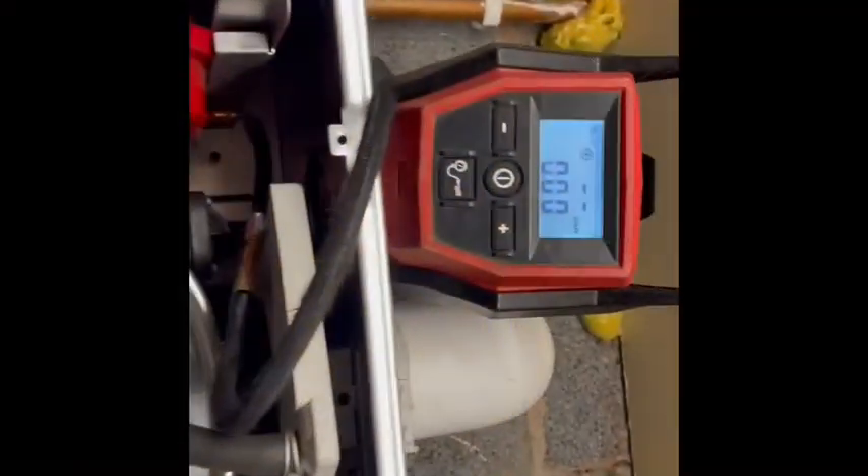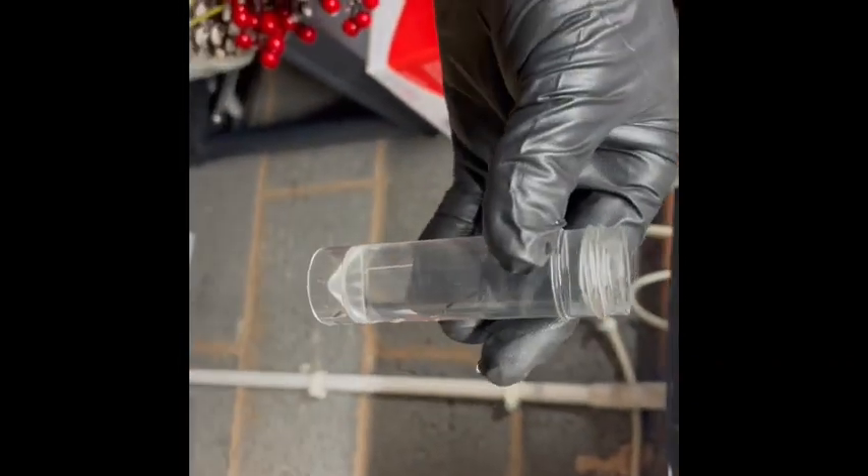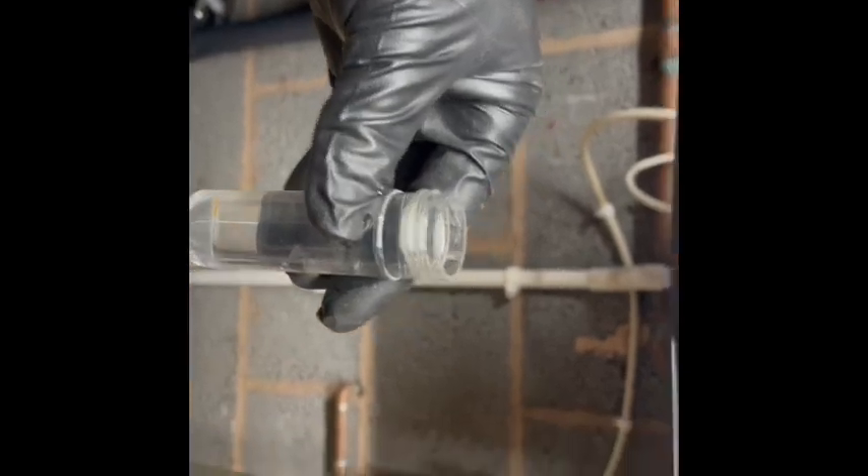The expansion vessel is completely flat — standard. So we've drained it down, we've taken a little water sample as well, let me test that for the customer over here, and get some charge back into this expansion vessel.